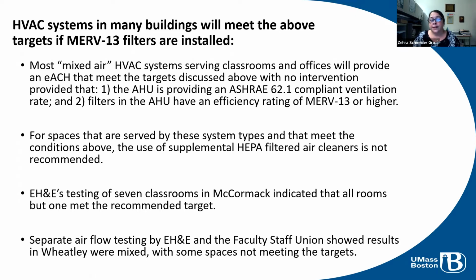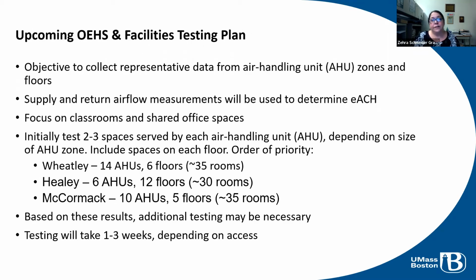We have brought in a consultant, as I mentioned, environmental health and engineering, who inspected all of our air handling units, but we also had them do some testing in some classrooms in McCormack and Wheatley. Their testing of 7 classrooms in McCormack indicated that all the rooms but one met the recommended target of 4 air changes per hour. In Wheatley, separate airflow testing by both environmental health and engineering and the faculty staff union showed results were mixed and that some spaces didn't meet the targets. So based on those results, we have developed a testing plan to look at some of the spaces in these buildings that will be upcoming.